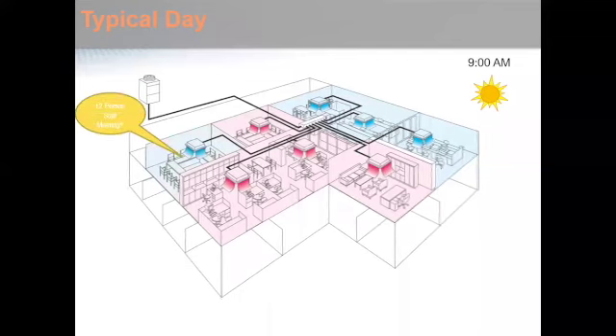Then the day is moving along a little bit further. We might have a 12-person meeting in the conference room, some kind of board meeting. That zone, because of the load in that space, is also going to require cooling. And this is going to be an ideal scenario for our heat recovery, as we discussed earlier. We're showing the 4 zones, the 3 on the eastern facing facade and the 1 conference room, all requiring cooling, and the more central zones in the middle of the building that don't see a lot of solar load or any other load are still going to be in heating mode. This is going to allow that condensing unit to ramp down all the way to 50% and only provide enough energy to cool the spaces that require cooling, then recycle that energy into the spaces that need heating.